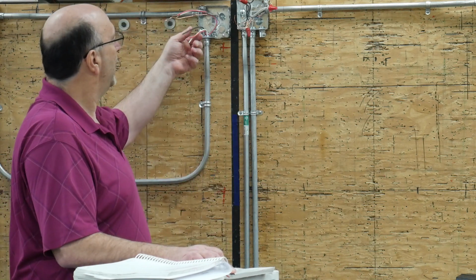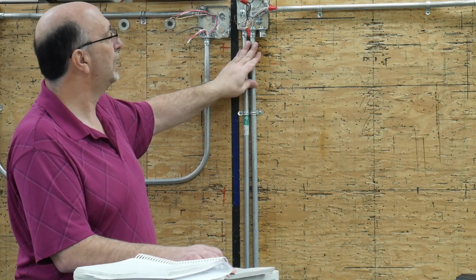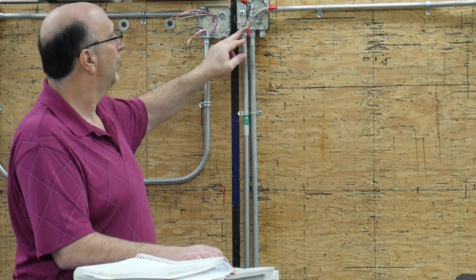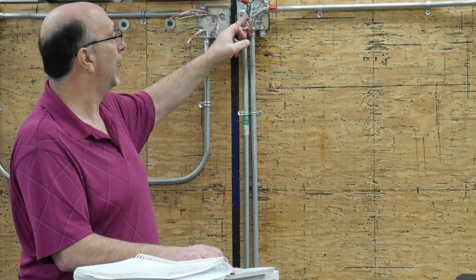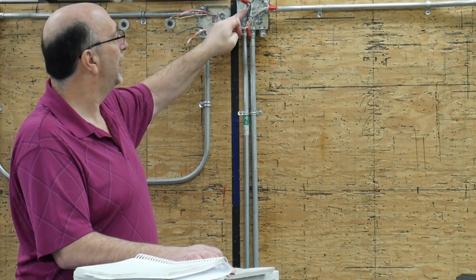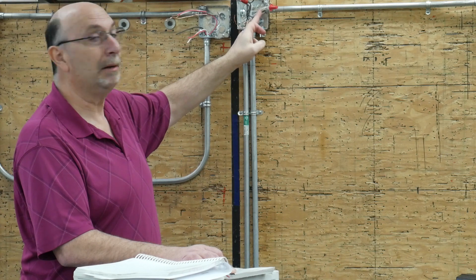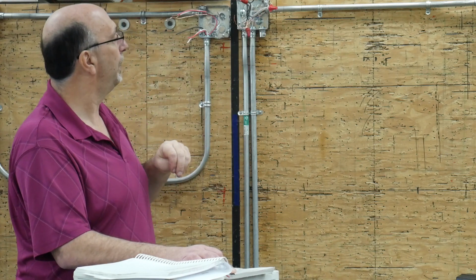Sub-rule B, each insulated conductor entering or leaving a box and connected to a terminal or connector within the box shall be considered as one insulated conductor. So in this example here, we have three runs of conduit. The three, for example, black conductors are all connected to each other with one common wire nut. These count as three conductors within the box. Much like the white conductor right here counts as three conductors within the box.